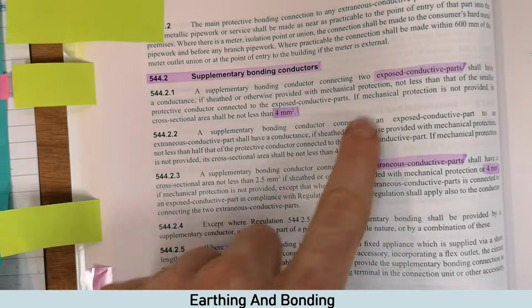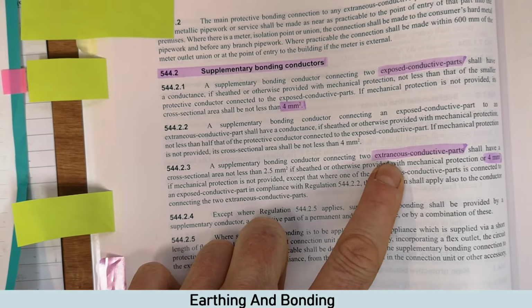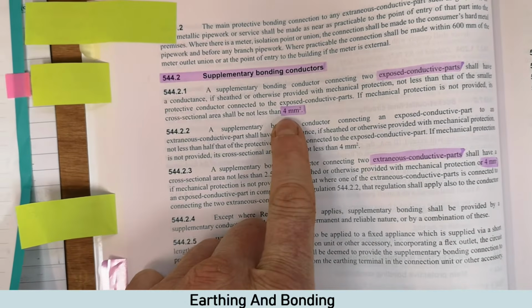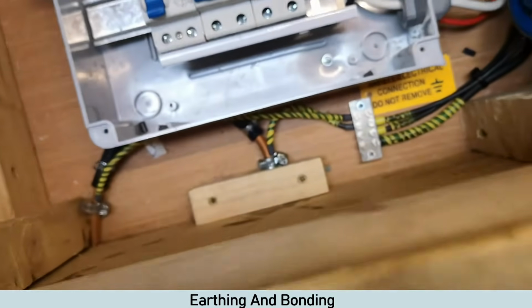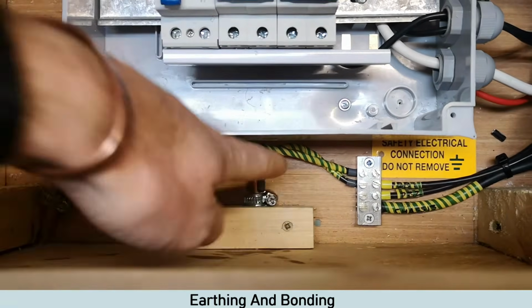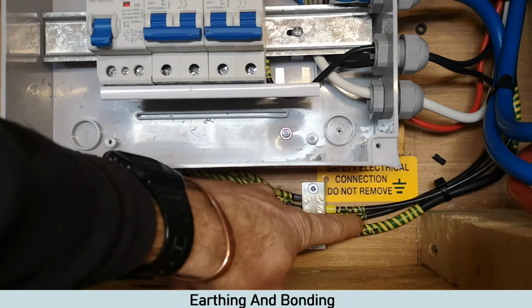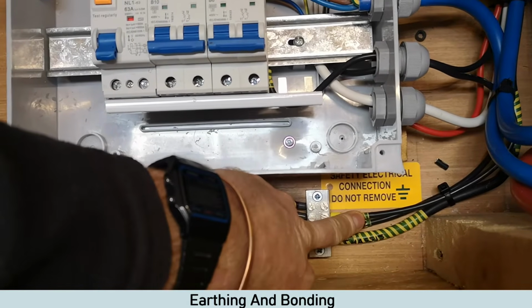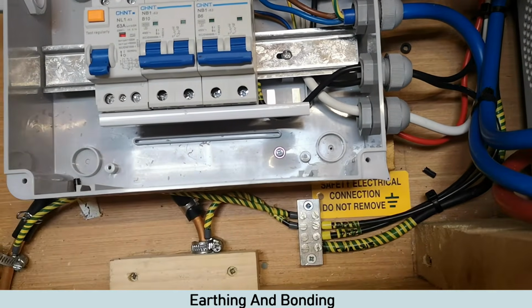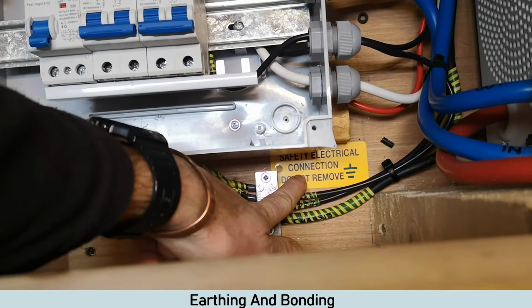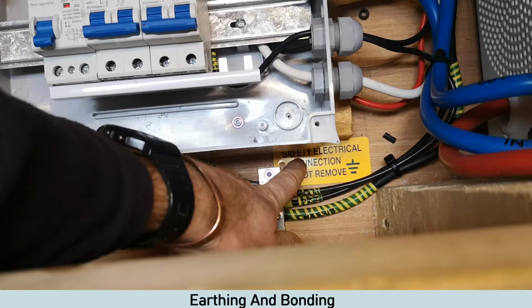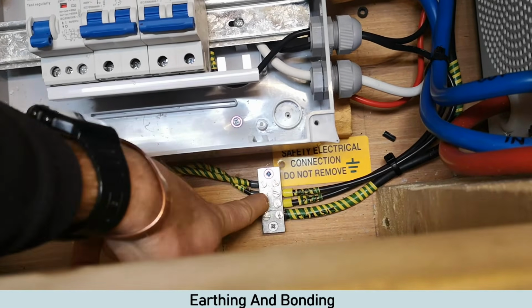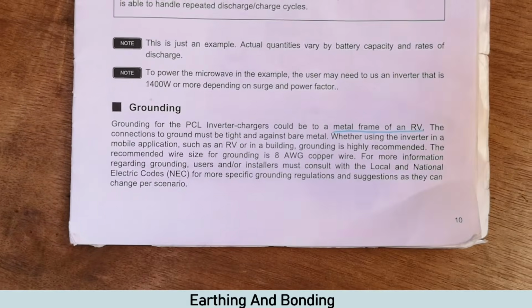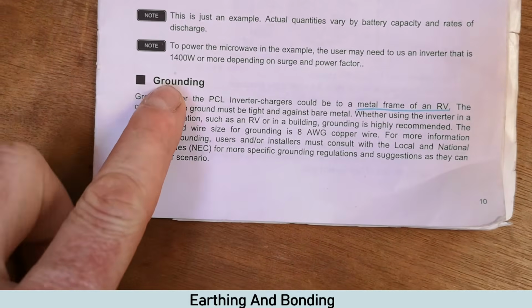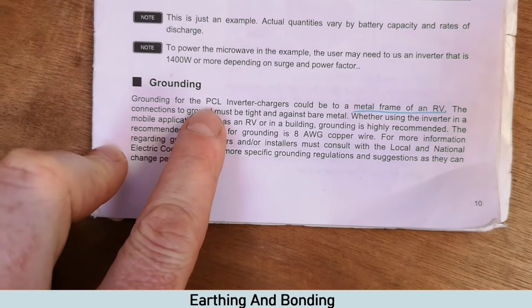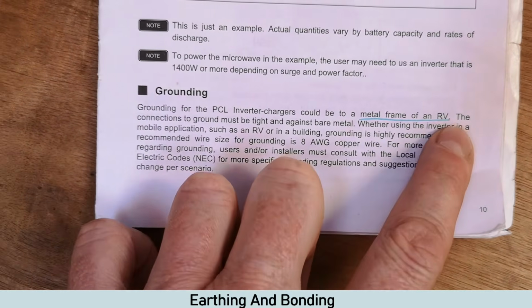Supplementary bonding conductors for exposed and extraneous conductive parts, which is like our pipe work, must be not less than 4mm. In ours, because we had cable left over, rather than buying 4mm, this is 6mm and these two are 6mm. But you could get away with 4mm if you wanted to, which meets the regulations. The last thing on bonding is this label here. You must have a label, safety electrical connection, do not remove, at the main earth terminal. A last note on earthing and bonding is this grounding section in the manual here. It recommends to bond the inverter chargers to the metal frame of the RV.